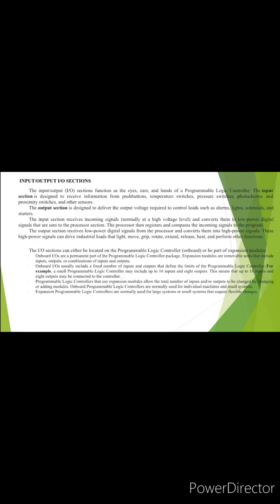Input and output sections. The input and output section functions as the eyes, ears, and hands of a programmable logic controller. The input section is designed to receive information from push buttons, temperature switches, pressure switches, photoelectric and proximity switches, and other sensors. The output section is designed to deliver the output voltage required to control loads such as alarms, lights, solenoids, and starters. The input section receives incoming signals, normally at a high voltage level, and converts them to low power digital signals that are sent to the processor section.